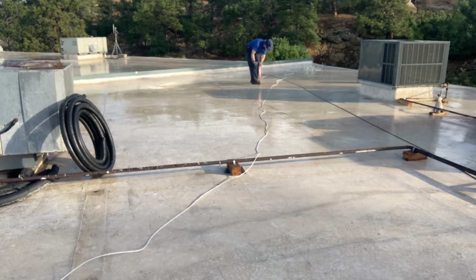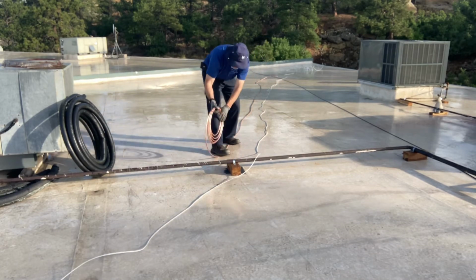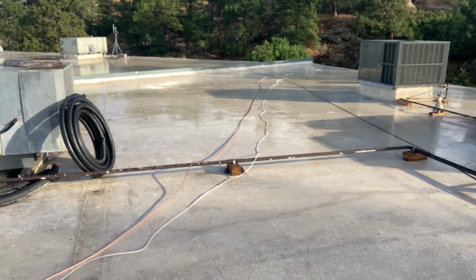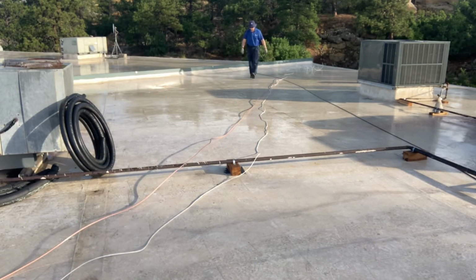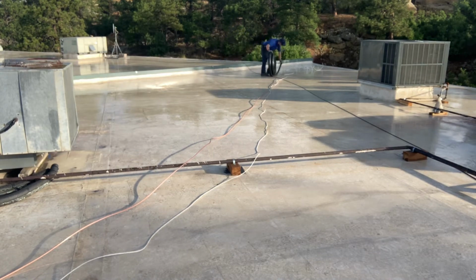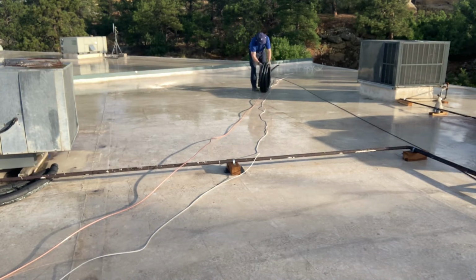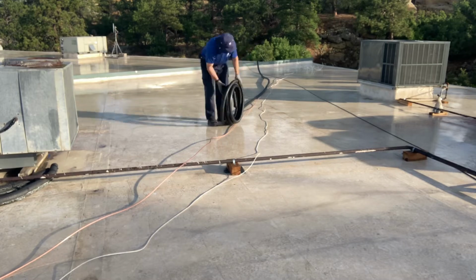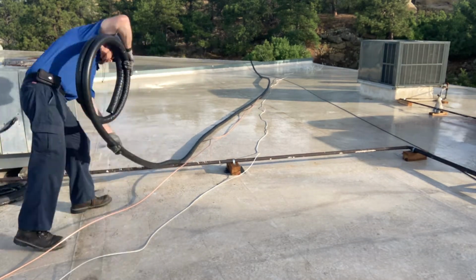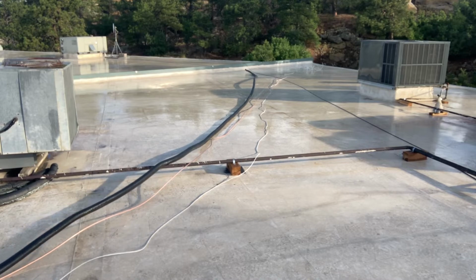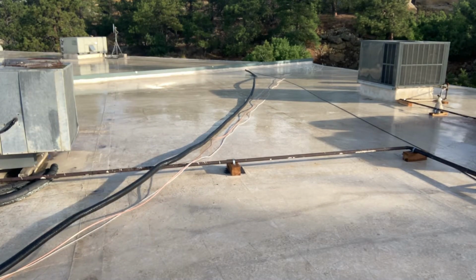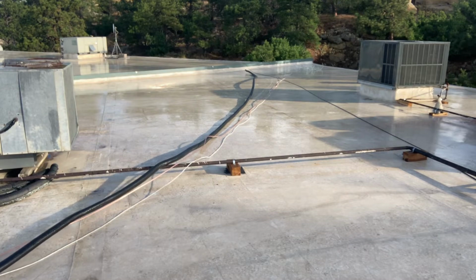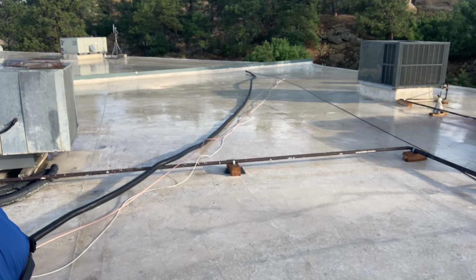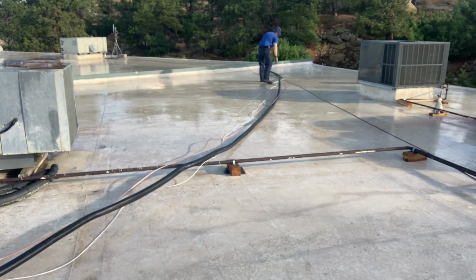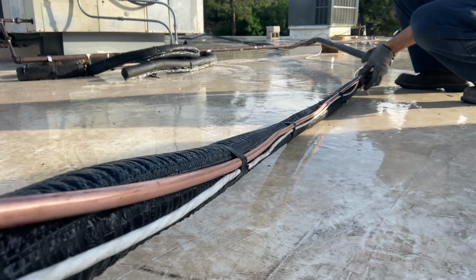So I got the thermostat wire stretched out. I'm going to go ahead and lay out the new line set with it, and I'll use electrical tape to tape the line set and the thermostat wire together every 2 feet or so to make it easier to feed it down from the roof 3 floors below to the first floor where the new air handler is. And to do that, I'm going to have a couple of gentlemen help me do that off camera. Again, because we want to reduce the risk of accidentally damaging or kinking our new line set.